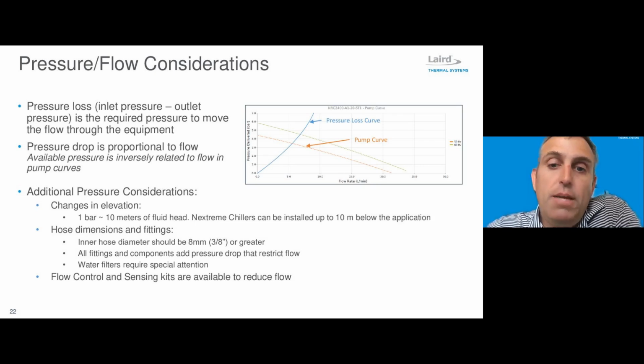So we need to keep in mind that this is kind of a double-edged sword here: applications that need more and more flow present two challenges. More flow means more pressure drop in the system, and at the same time, a given pump is capable of less pressure at a higher flow. So it's a delicate balancing act.